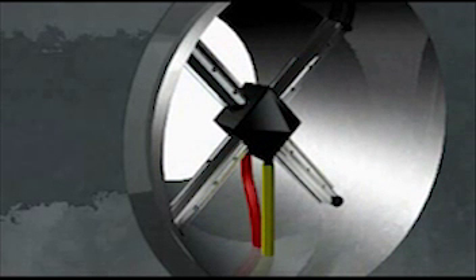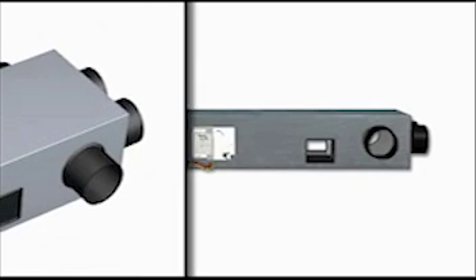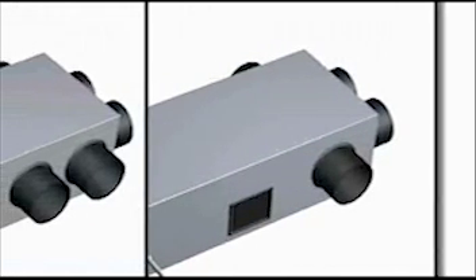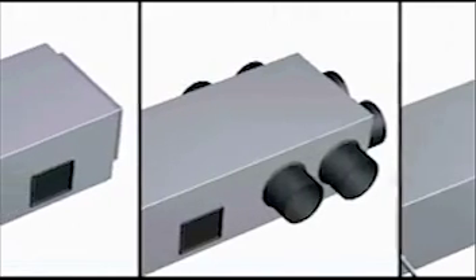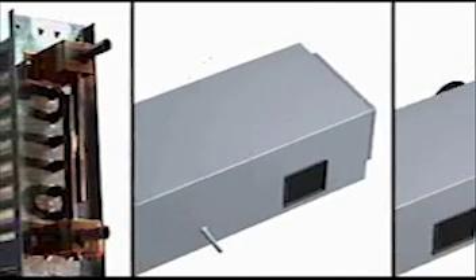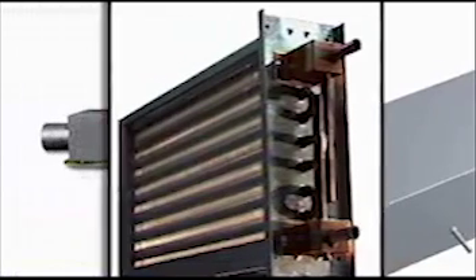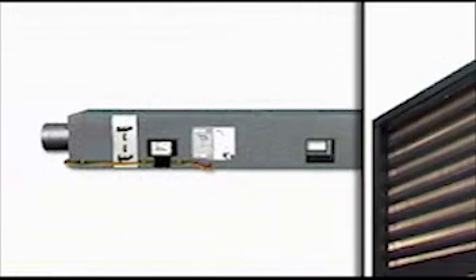The induction effect is demonstrated with smoke. The primary air volume is measured at the inlet of the terminal with the flow cross sensor. This patented sensor measures and averages the air velocity over at least 12 test points equally distributed over the duct area. The induction VAV terminal is provided with 4 circular outlets. Optionally, the unit can be supplied with 6 circular or 1 rectangular outlet spigot. For reheat purposes, the terminal can be supplied with a hot water or electric reheat coil.